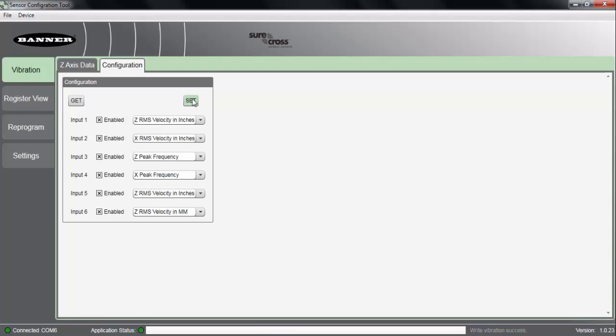and now when we connect our vibration sensor to a wireless network, the registers that we will be pulling in through the gateway into our PLC or wherever that information is ultimately going to will now be these new parameters that we have updated, rather than the default of just one axis and velocity in both millimeters and inches per second.